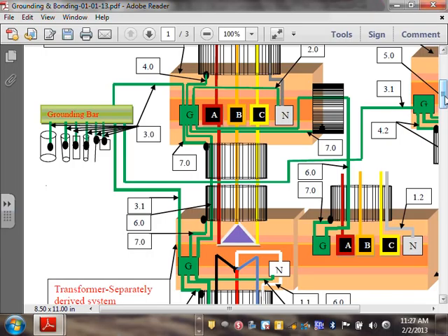On the primary side of the transformer, you have to pull an equipment grounding conductor. Did we label it here? Number 6. Can you guys see that? Number 6, equipment grounding conductor. You have to pull an equipment grounding conductor between the main panel and the transformer. And you also have to bond the bushings, if it's rigid, if it's not PVC, on both sides. That would be number 7.